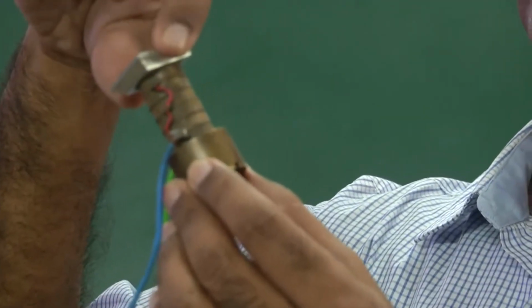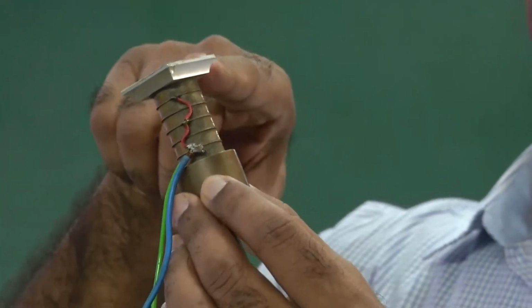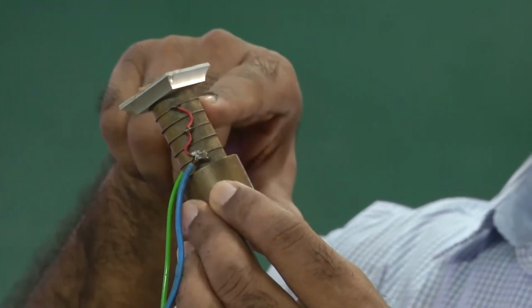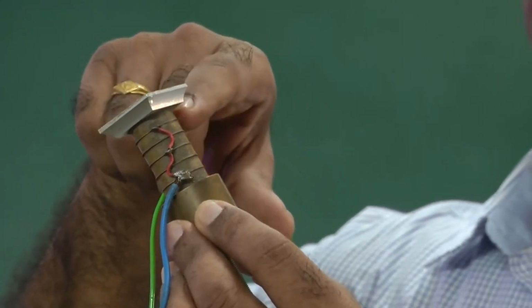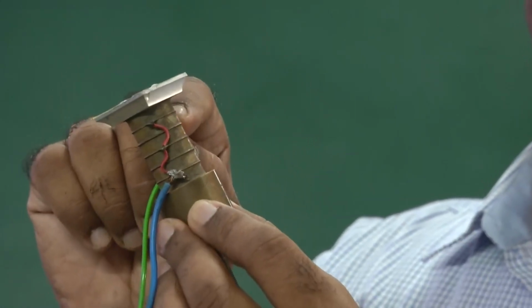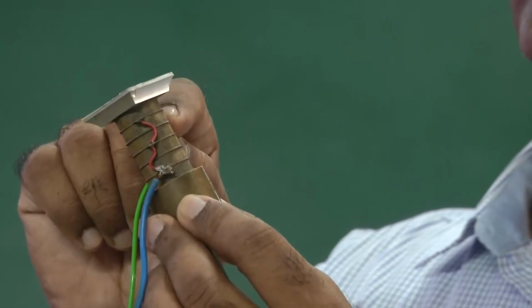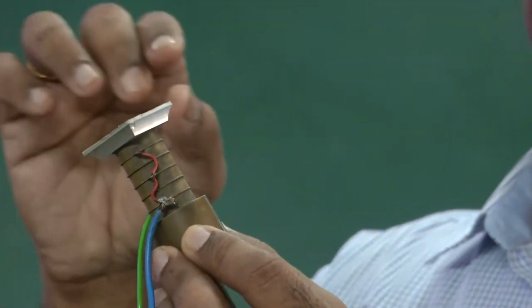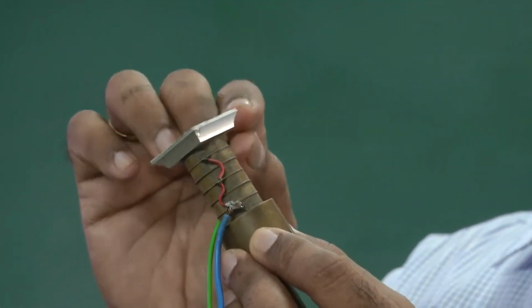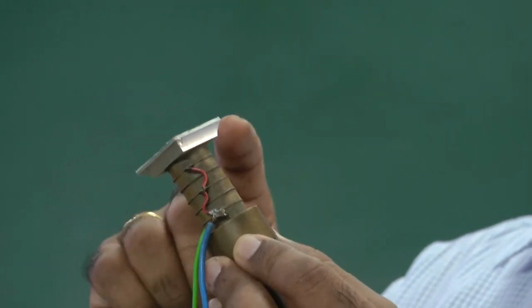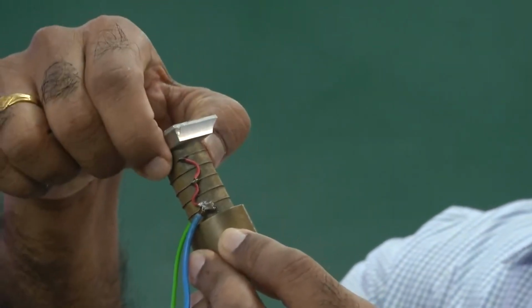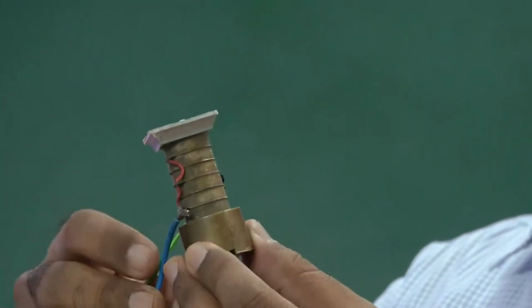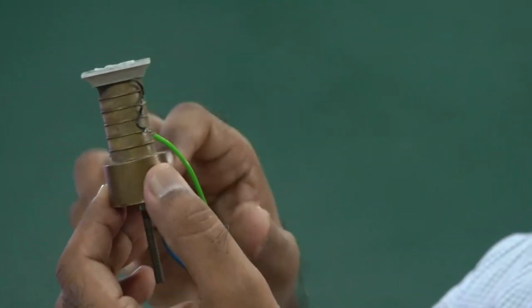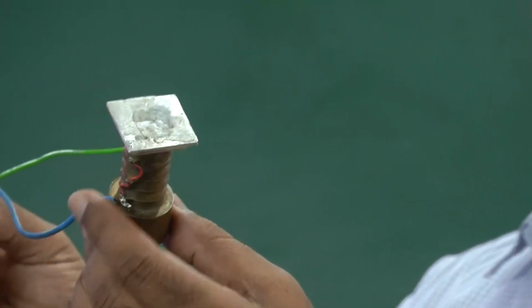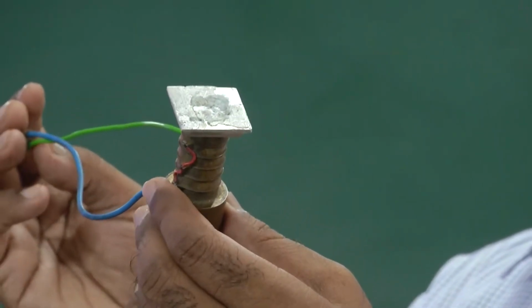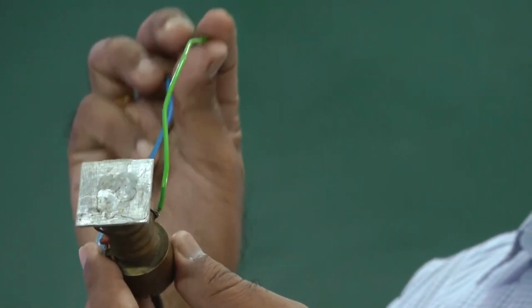There is a front face which we call a head, and between the head and the mass you would observe 6 piezo discs which are mounted, and the discs are separated. Each piezo disc is separated by an electrode, and the electrode has an epoxy layer on either side separating it from each piezo disc. So, there are 6 of these piezo discs, and each disc is separated by an electrode, and these electrodes are all connected, as you notice here, and the wires connecting the electrodes are taken out, and we are going to feed the signal through these wires.